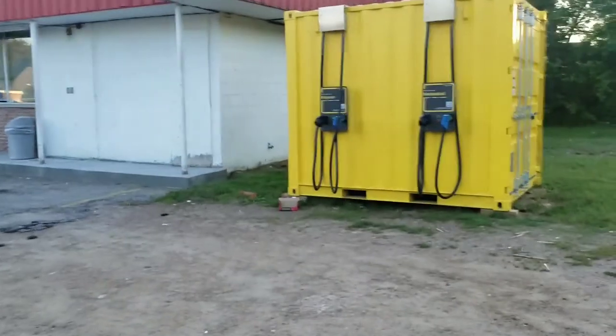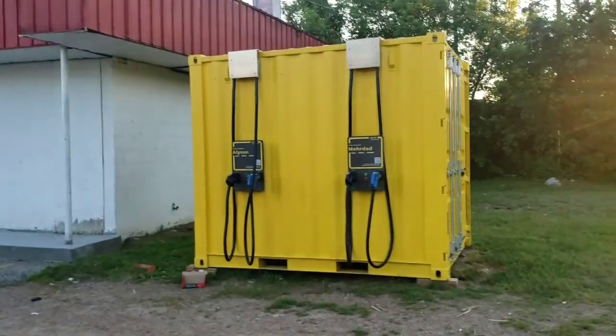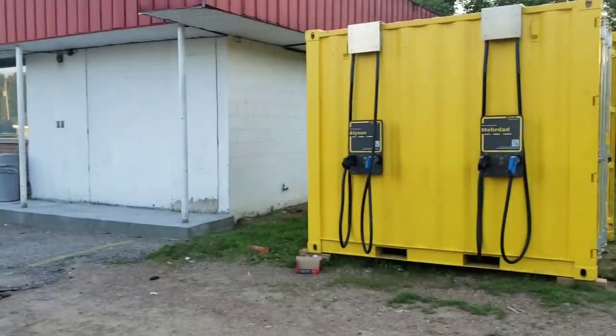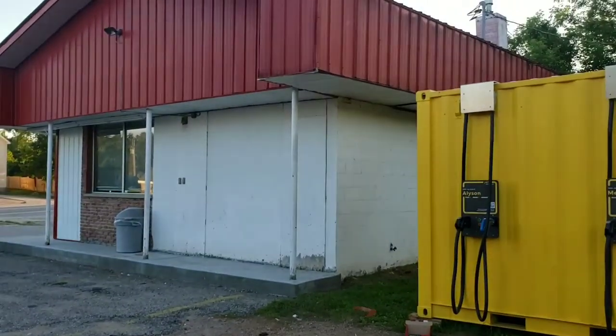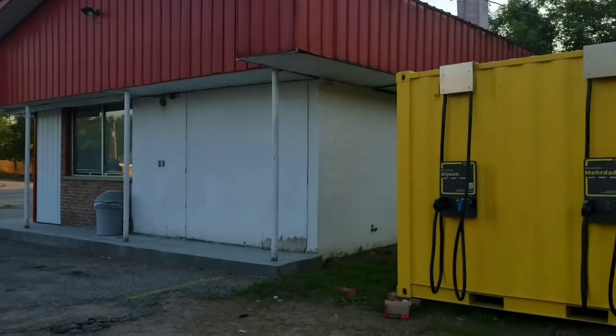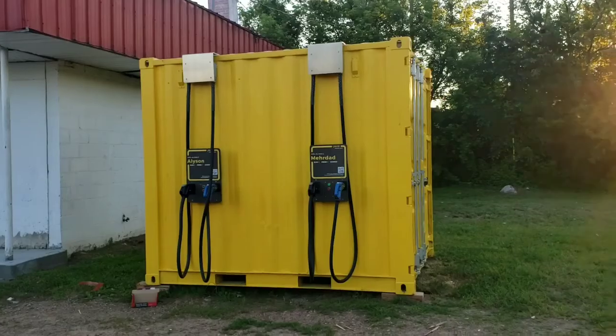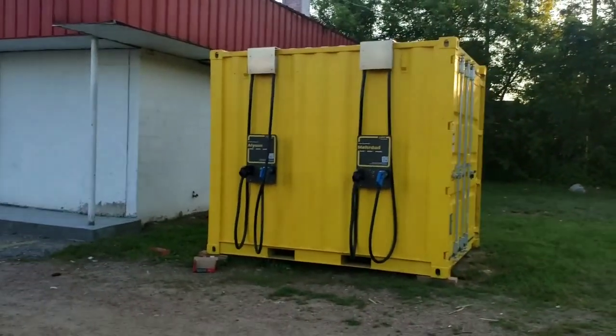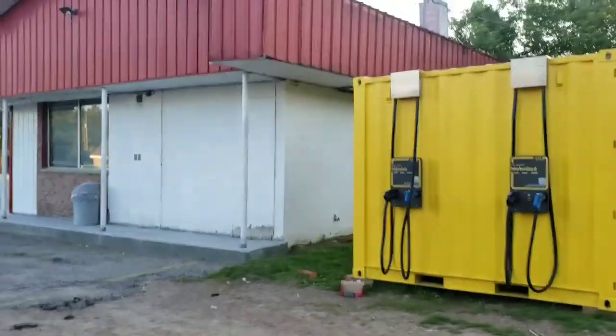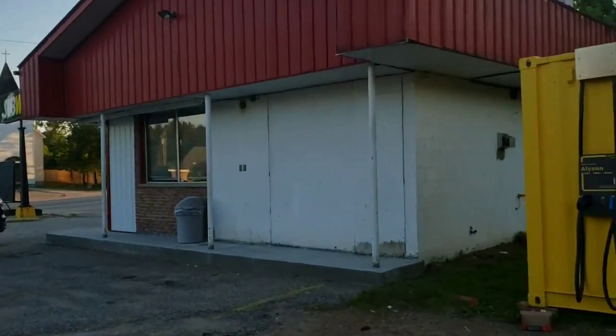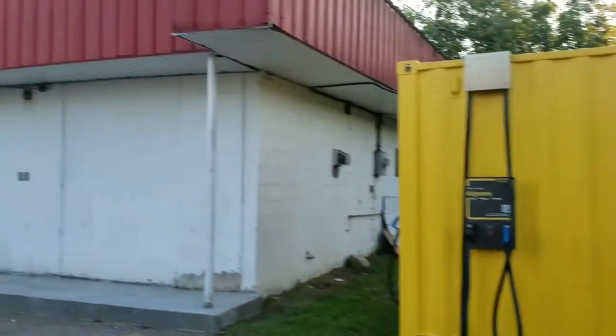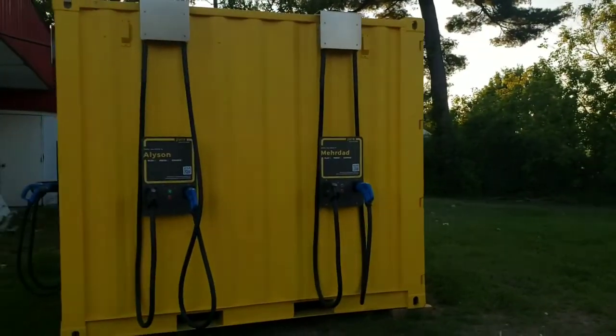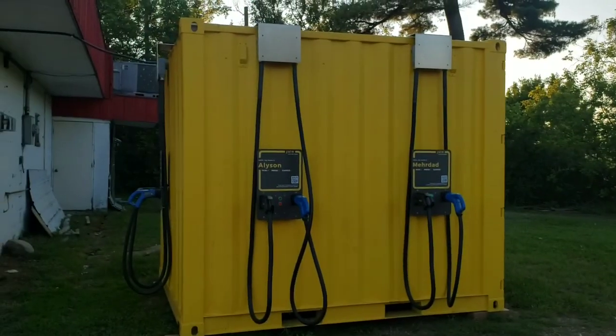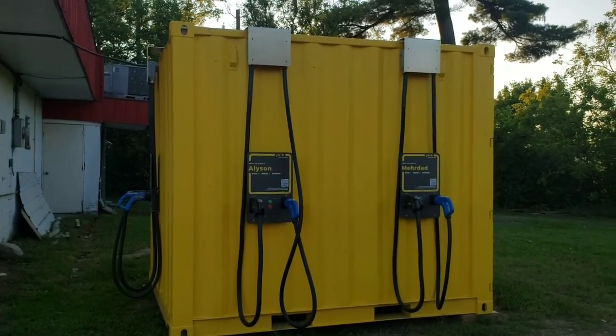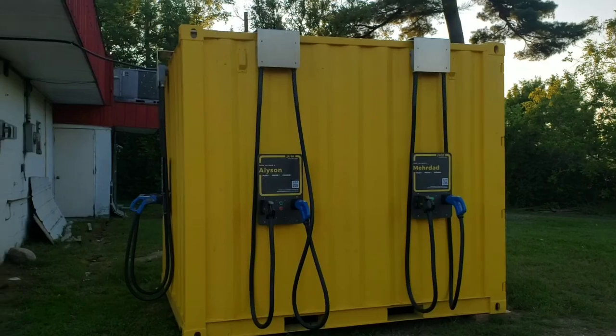Remember, guys, de-energize the charger and then start attacking the fire. Be cognizant that we may have exposures already being impinged by fire upon arrival. So if we have to put an exposure line to the building prior to shutting down the charger, we can, but we cannot fight the charger fire until the electrical power is shut down.